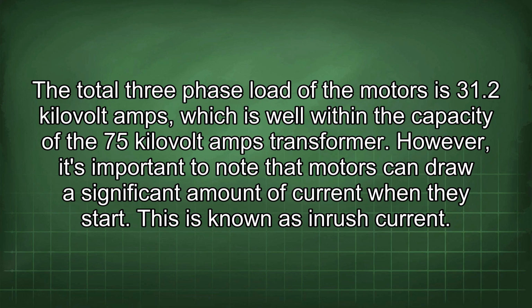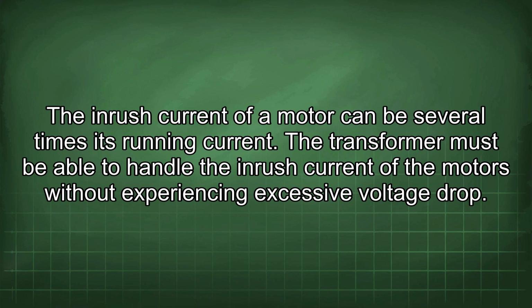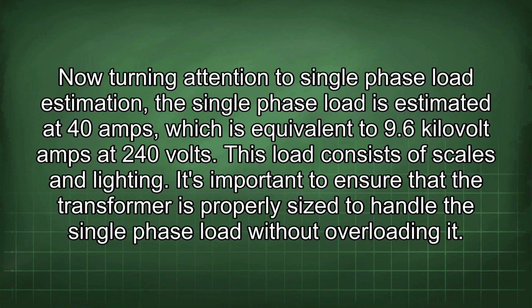kVA transformer. However, it's important to note that motors can draw a significant amount of current when they start. This is known as inrush current. The inrush current of a motor can be several times its running current. The transformer must be able to handle the inrush current of the motors without experiencing excessive voltage drop. Now turning attention to single-phase load estimation, the single-phase load is estimated at 40 amps, which is equivalent to 9.6 kVA at 240 volts.